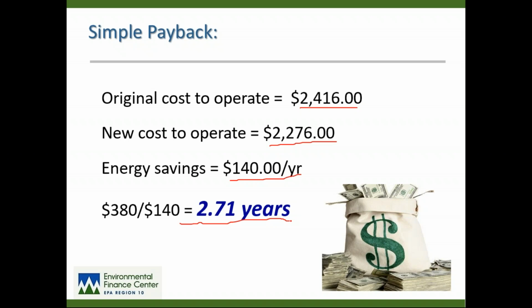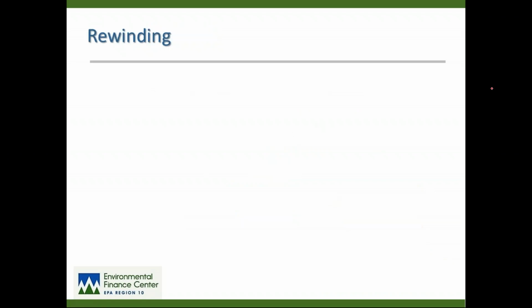Now, the typical operating life of a motor is 10 years or more. So in this example, the cost of this motor is going to be completely paid back in less than 3 years. And the energy savings beyond that just keeps compounding year after year after year. And again, if you have 20 or 30 motors like this in your facility, upgrading to premium efficiency can save you really a lot of money. That's, again, the bottom line of this workshop.